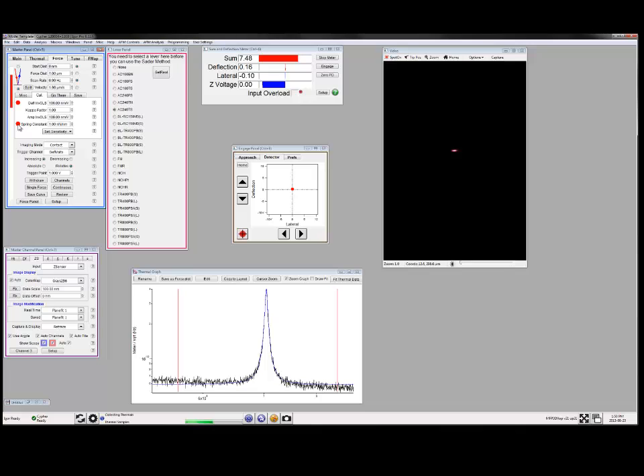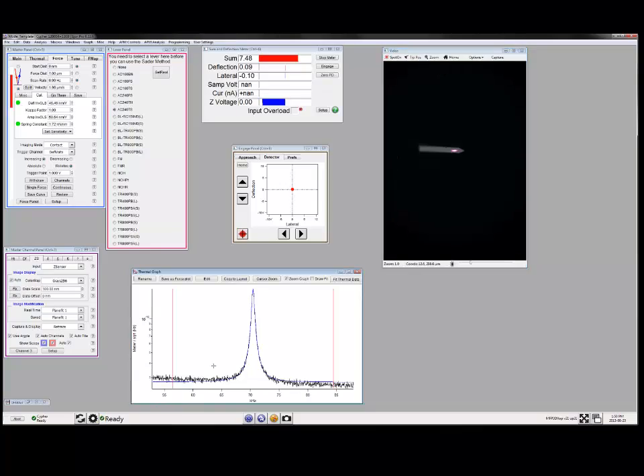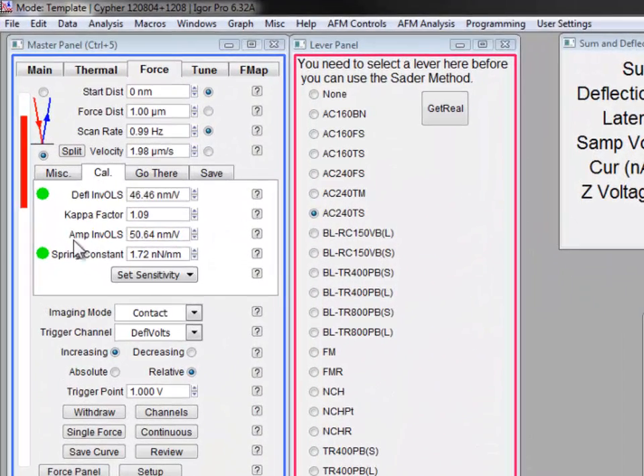As the procedure runs, you can see the thermal here in black, the blue line is the model fit, and the red is the bounds of the fit. And at the bottom left, you can see a status bar as the procedure goes forward. Once it's finished, you'll see that I have my results, which shows that my deflection invols is 46.46 nanometers per volt, and my spring constant is 1.72 nanonewtons per nanometer, which is totally what I would expect for this cantilever.